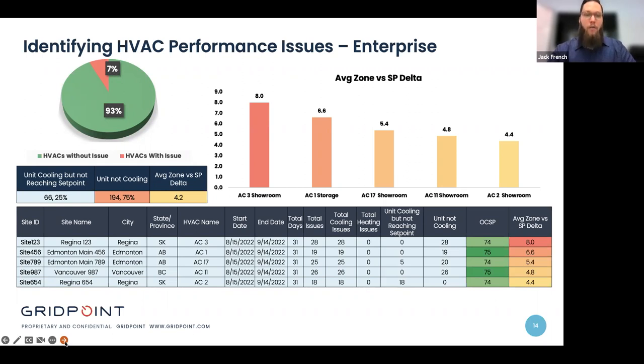Then finally, the far right-hand column in that table just below the pie chart, average zone versus set point delta. So for all of these units that have had exceptions, on average, how far away from set point were they? 4.2 degrees. So this is an important report to run, maybe even monthly or quarterly, and it's going to change seasonally. So we're going to see heating exceptions in the winter, cooling exceptions in the summer. And then you may see a mix of both in the shoulder season, depending on what the temperature is like on any given day.